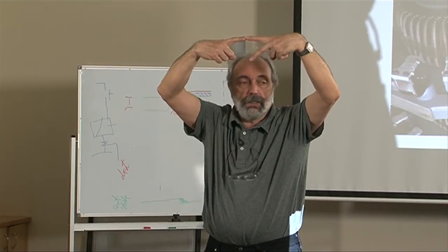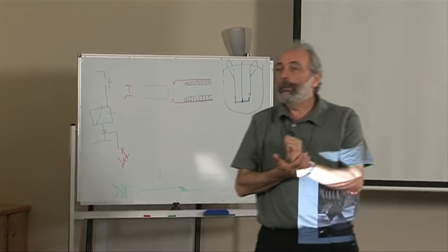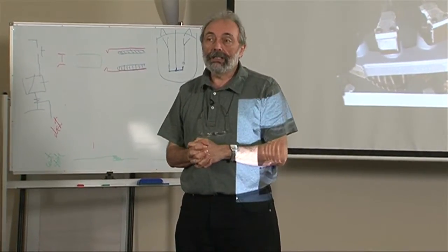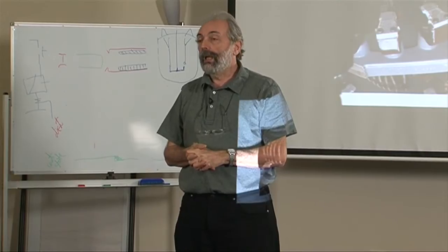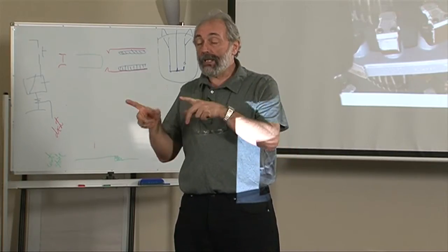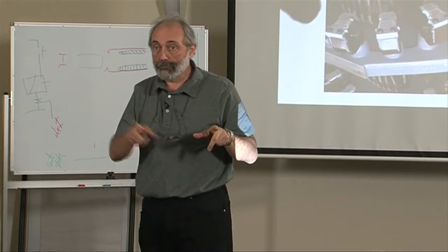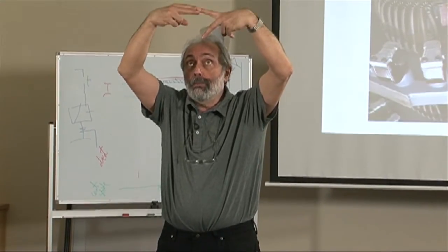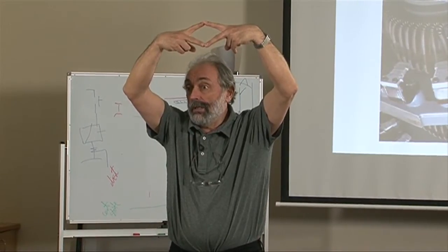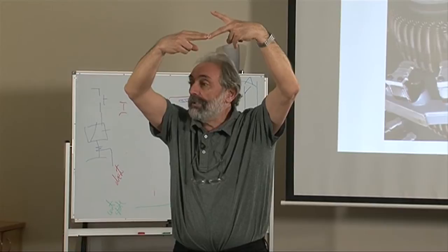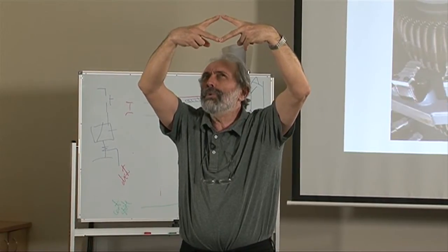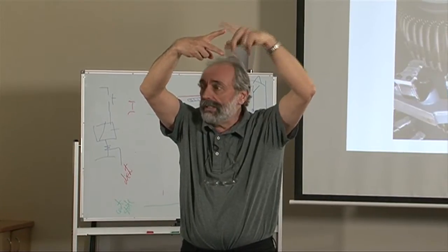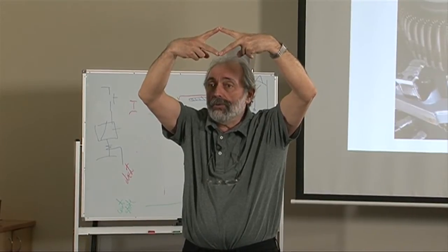So how do you change from one position to another? Well, the smart guy was Dr. Janssen who patented a process. It was called the Janssen switch for many years in 1927. He said you should make before break by having two connectors. So what you do is you make with the next contact, next step before you break from the previous. But what do you do during the millisecond that it is shorted? You have circulating current, short circuit current. So how do you minimize it?